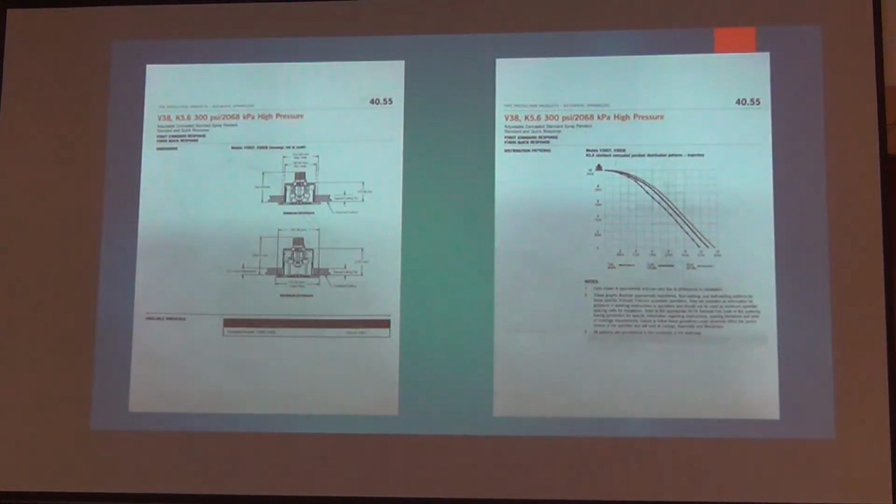That's what it does. That cover drops down, this drops down, that's your deflector. There's a fusible link right inside. And this one looks like 205. At 205 degrees, the fusible link lets go, the bar comes out, hits the deflector, and designs to the pattern on this head. And they are strictly tested to distribute water in set patterns throughout the coverage area.